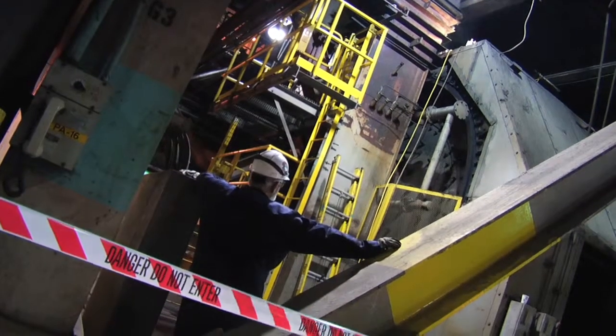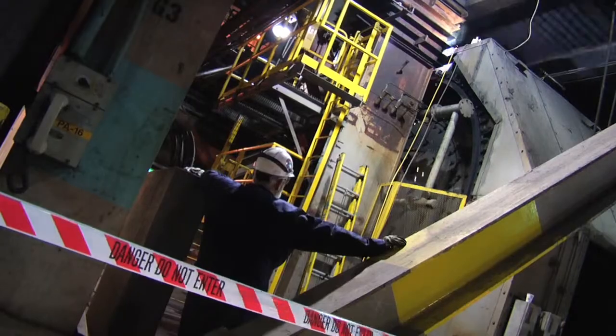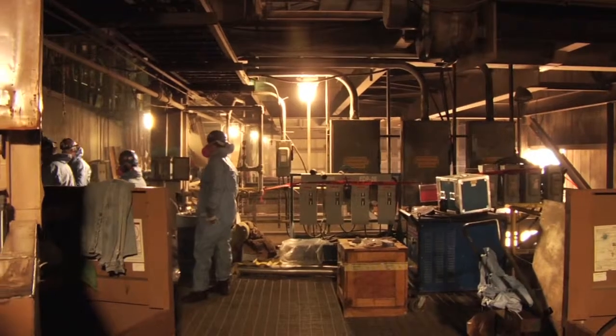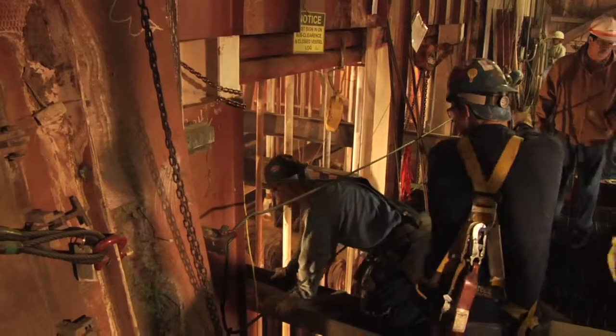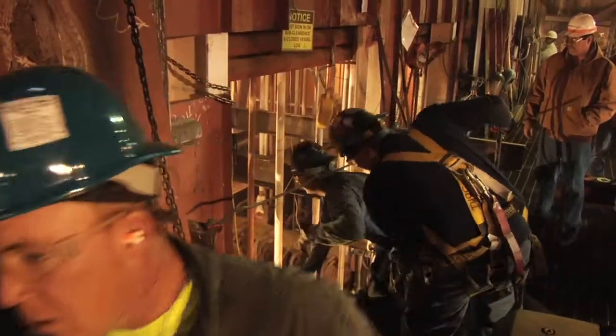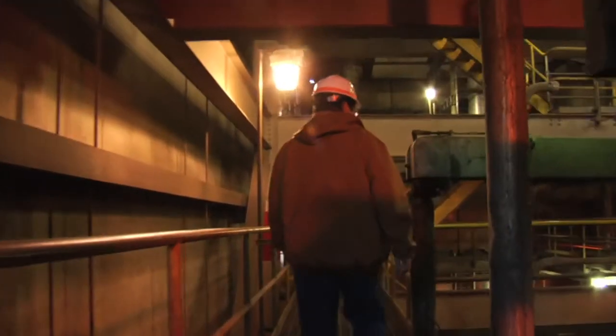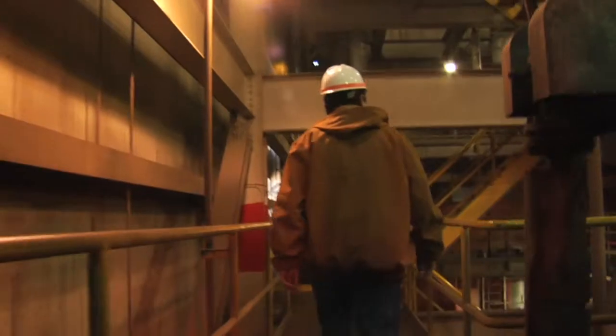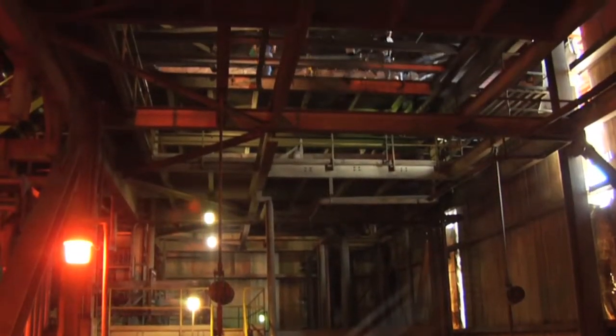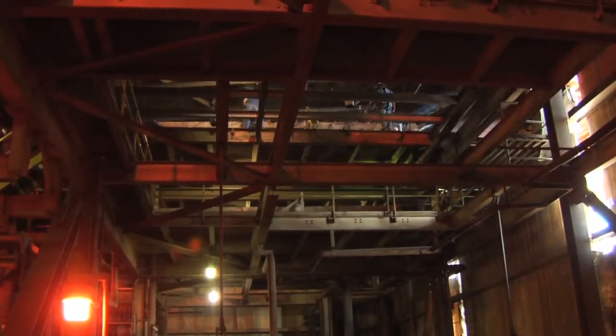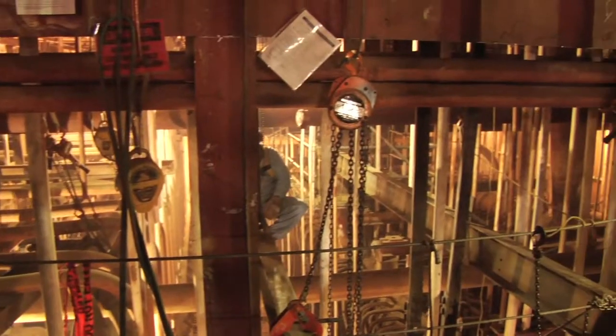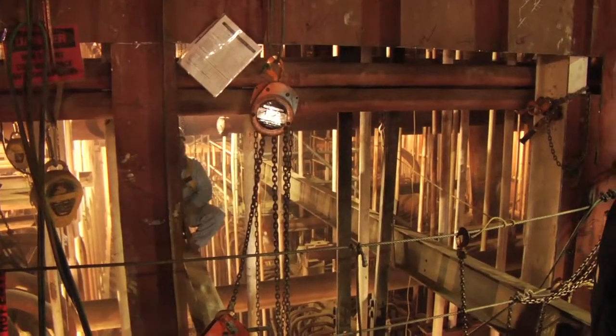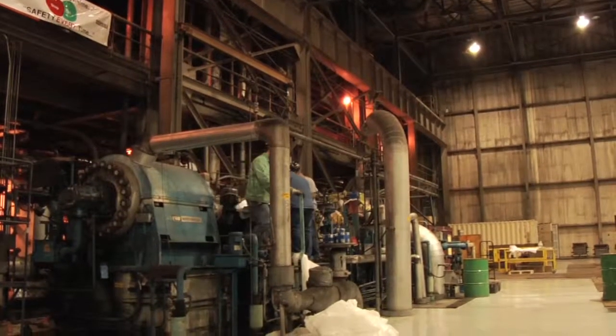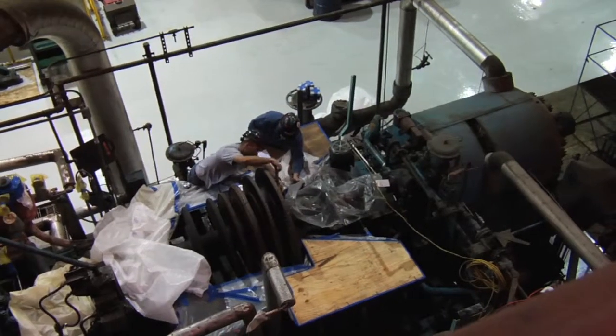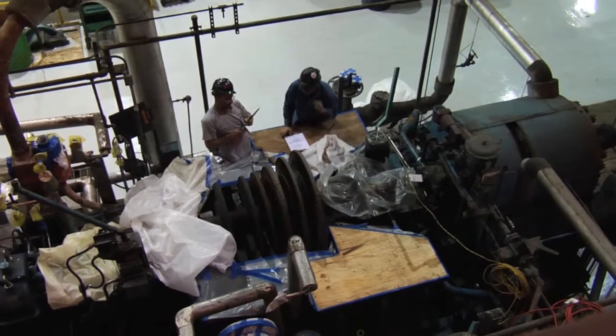For contractors working at Hoosier Energy, the foreman or designated lead person shall walk down each applicable clearance to verify accuracy and sign on to the Hoosier Energy clearance prior to commencing work on normally energized equipment. A contractor sub-clearance will then be issued to the foreman or designated lead person. Each affected worker will need to sign on the contractor sub-clearance prior to starting work and will sign off the contractor sub-clearance when the work is finished.